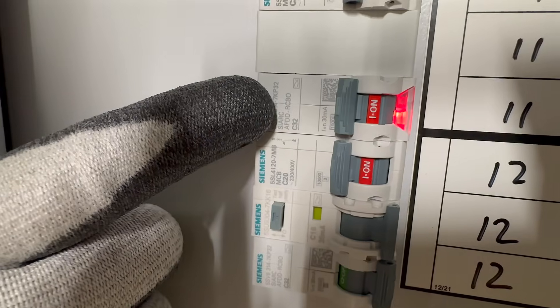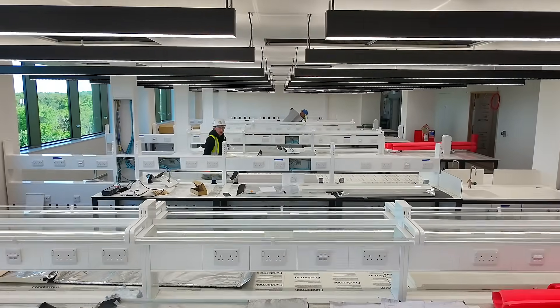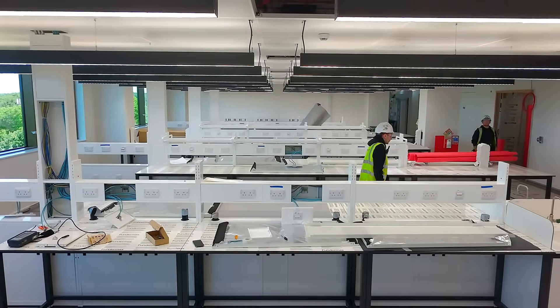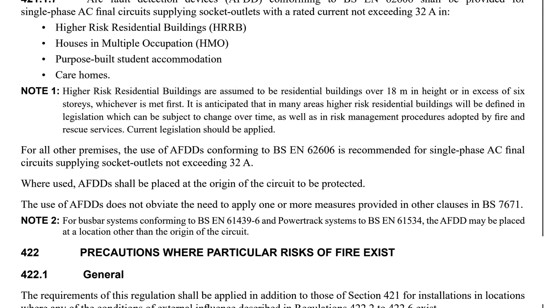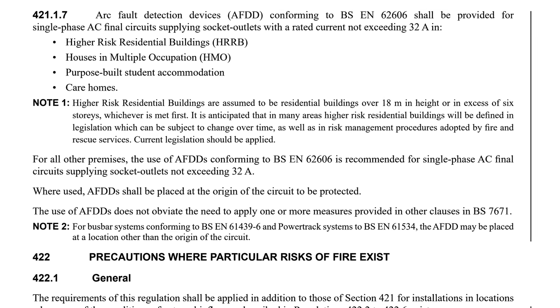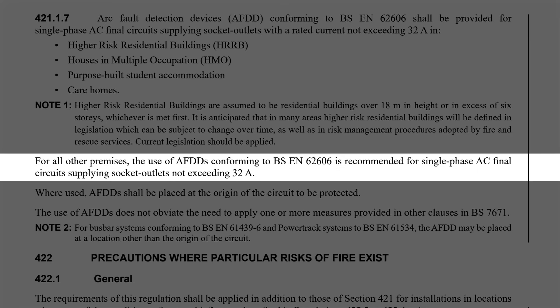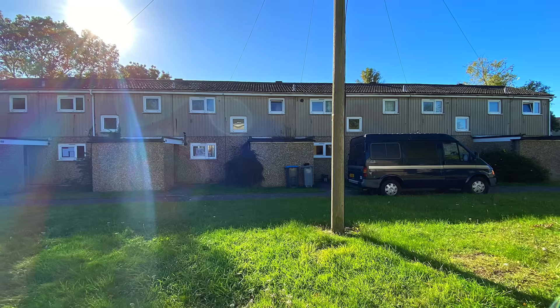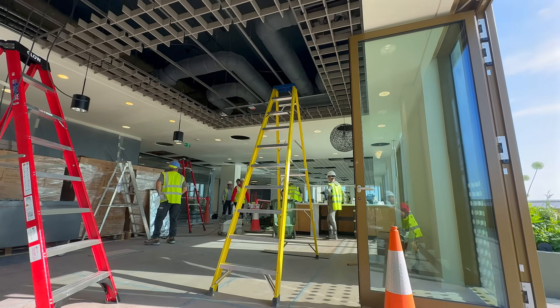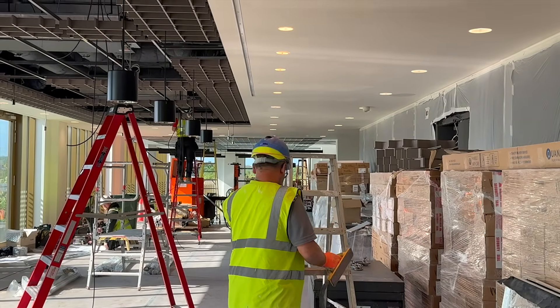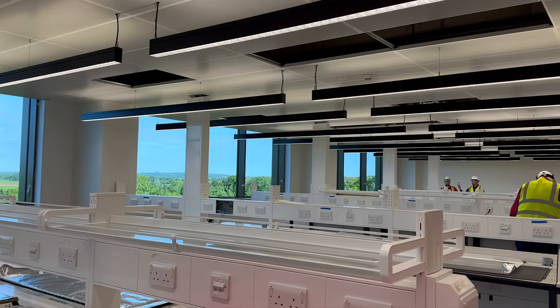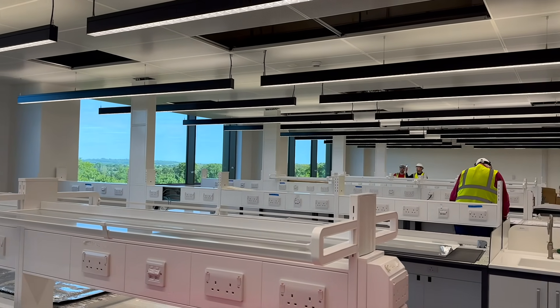Well, no. AFDDs aren't a regulatory requirement for this type of commercial install, but they are recommended under regulation 421.1.7 of BS 7671. This regulation advises the use of AFDDs to reduce the risk caused by arc faults in final circuits with a current not exceeding 32 amps, particularly in higher-risk residential buildings, houses in multiple occupation, purpose-built student accommodation and care homes. The designers on this commercial install have chosen to fit them on all socket outlets due to the sensitive nature of the equipment and the superior protection offered by AFDDs.